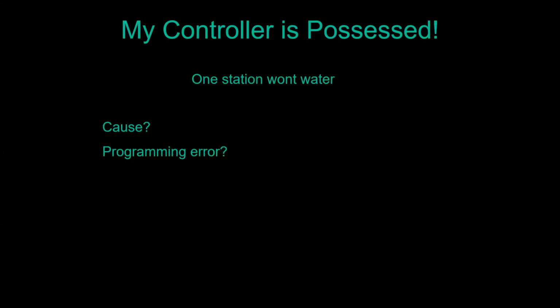So it could be a failure, either an electrical failure, the wiring going out to the valve, the solenoid on the valve. We're going to cover those. Now, even though these valves are getting an electrical signal from the controller to open, there's not a motorized gate inside there. They're using the water itself to push open that diaphragm and then push it back closed when it's time to stop running. So it could be what we call a hydraulic failure.